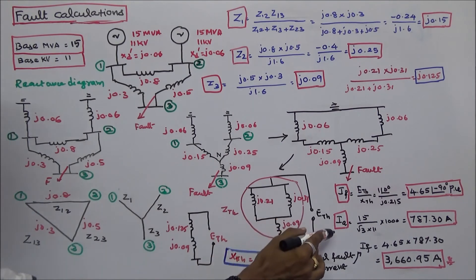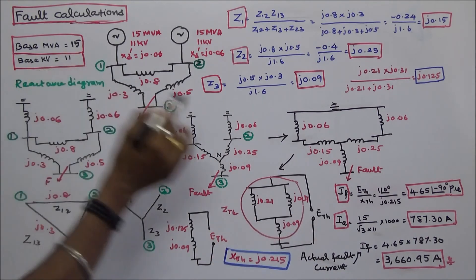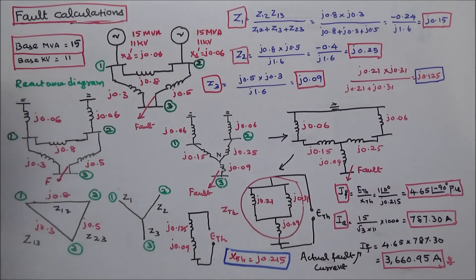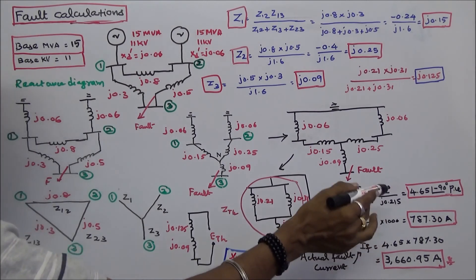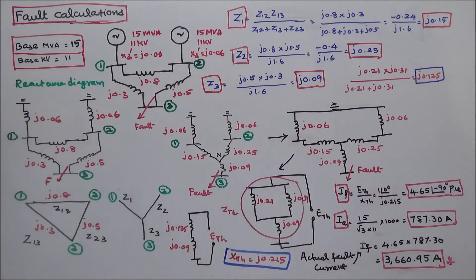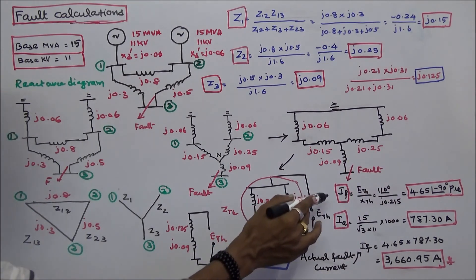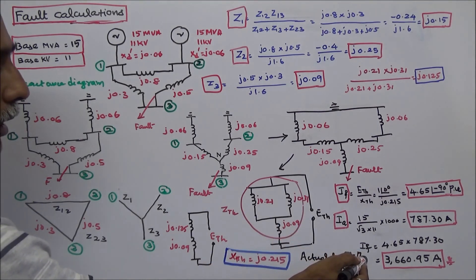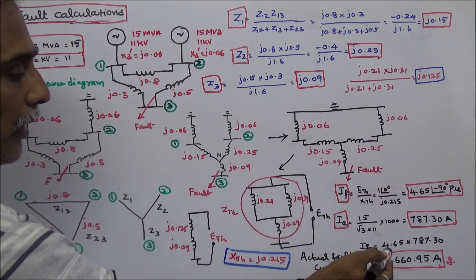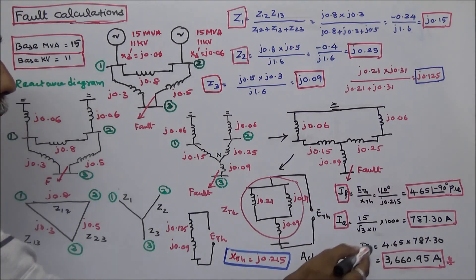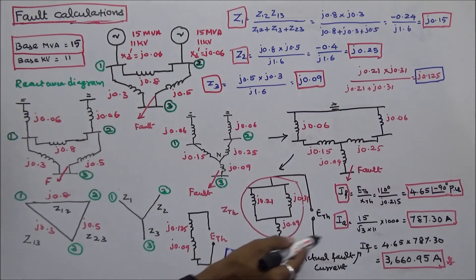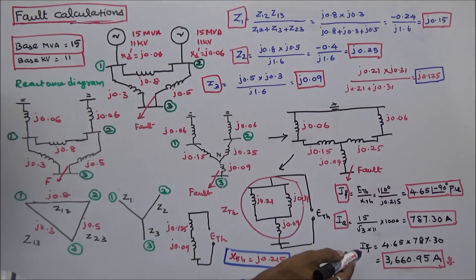Next, the actual base current is calculated as 15 MVA divided by root 3 multiplied by 11 kV, which equals 787.30 amps. Once the per unit fault current and base current are known, the actual fault current IF equals the per unit fault current multiplied by the base current: 4.65 multiplied by 787.30, giving an actual fault current of 3660.95 amps.